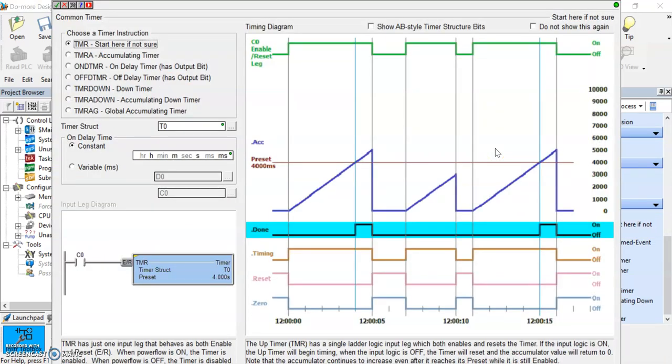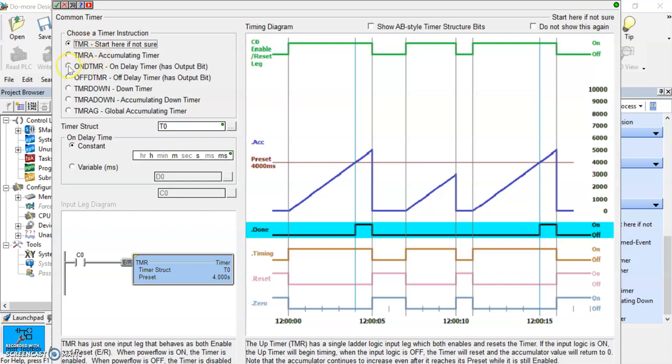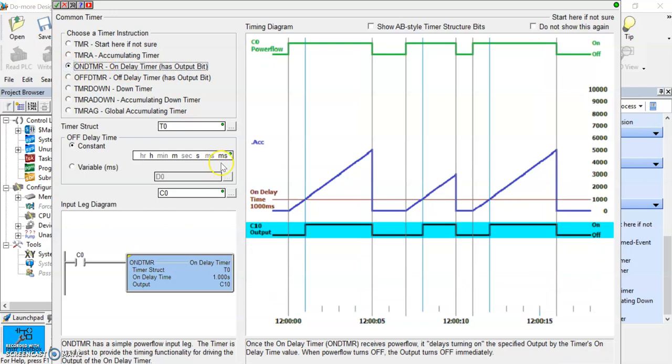And it opens up a dialog box here, which we need anyway because we have to tell the timer what its function is going to be. So it says here timers start here if you're not sure. In most cases we're going to be either using an on delay timer or an off delay timer. And each one of these it says has an output bit, which is good because that's what we want to do. We want to make our timer do something and have an output that it's going to associate. And we'll get into that and what that looks like. So let's select the on delay timer here.